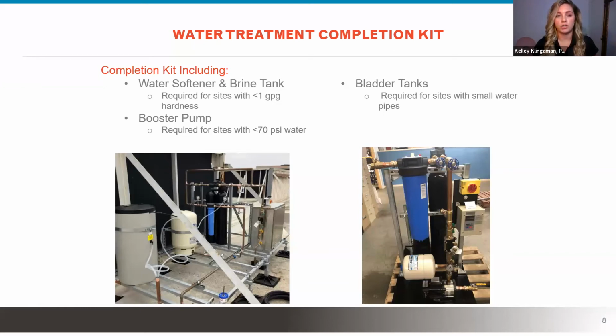What we're doing is pulling water off the building supply line and boosting it up to pressure—we need about 60 to 70 PSI at our frames. Then we run it through a commercial grade Kinetico water softener, which reacts with salt, the resin in the salt, so we have a brine tank as well, and a bladder tank to help prevent pipe knocking. Those two photos below are examples: on the left, it's sitting on a Bigfoot strut system to help disperse weight on a rooftop, and on the right is a prototype we're working on, pre-skidding all the equipment together so if it's going inside a mechanical room, it takes up less real estate.